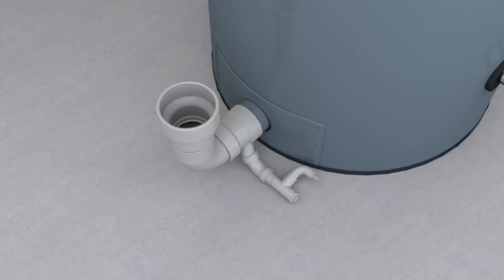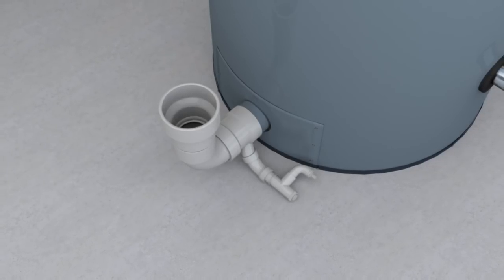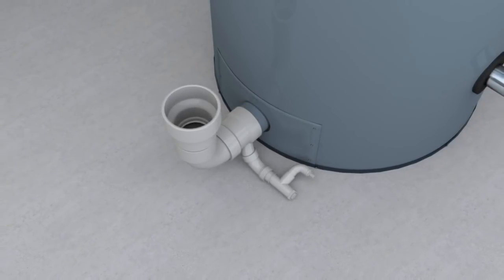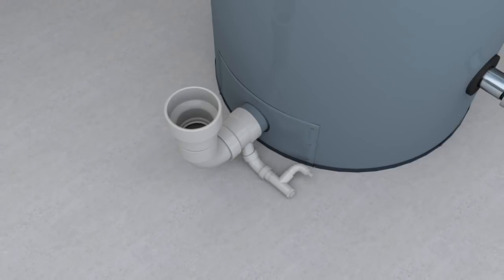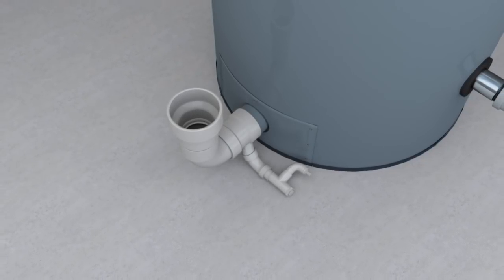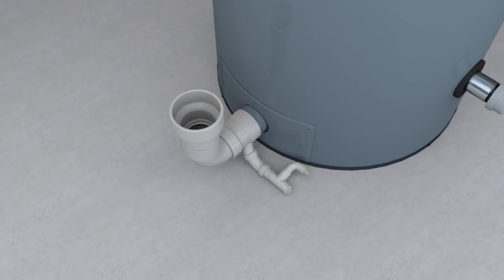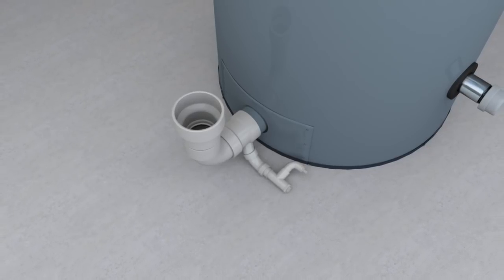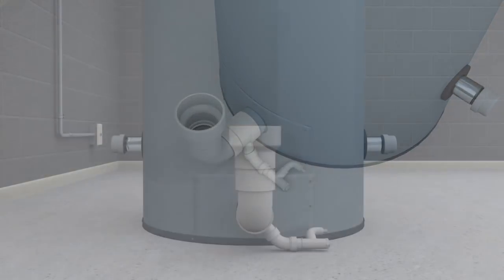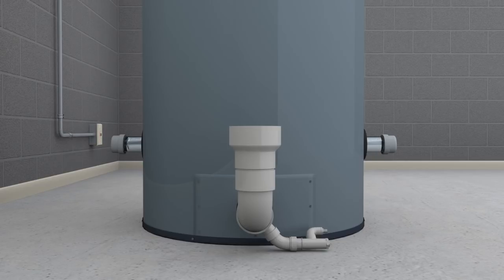During normal operation of the optiTHERM high-efficiency water heater, condensate is produced. The water heater is supplied with a pre-assembled PVC condensate elbow assembly that must be connected to the exhaust pipe prior to the exhaust venting connection. Be sure to correctly orient the condensate elbow and install with an approved high-heat silicone sealant.